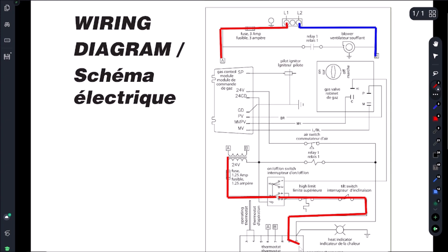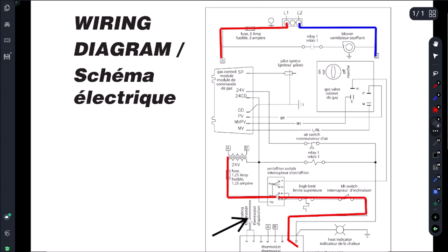So there's two reasons why this switch doesn't close. It's either this thermostat is bad or the thermostat's sending the correct signal to this board and this board is bad. So 9 out of 10 times I'm finding this board is bad.